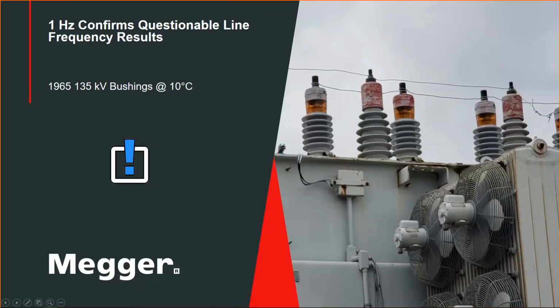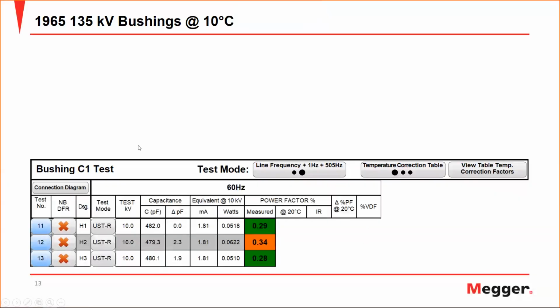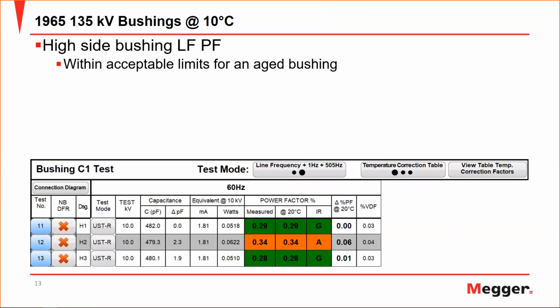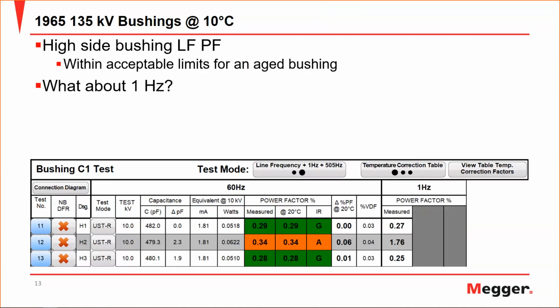Moving on, we are able to tell when a transformer allows us to validate when bushings are questionable or not. Here we see that we had another set of high side bushings tested at line frequency. These look within the acceptable limits ranged for an aged bushing. There's a small deviation from the nameplate in terms of power factor, but again, nothing too severe when only looking at line frequency and using the temperature correction tables. However, when we look at the 1 Hertz, we see that there is an elevated value for H2, which looks very much different than its sister bushings.